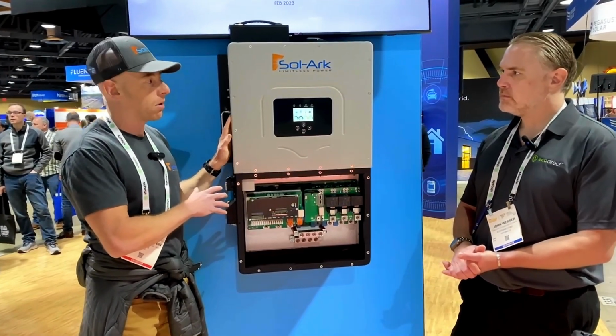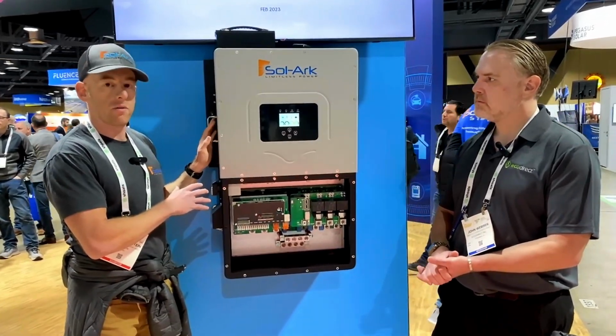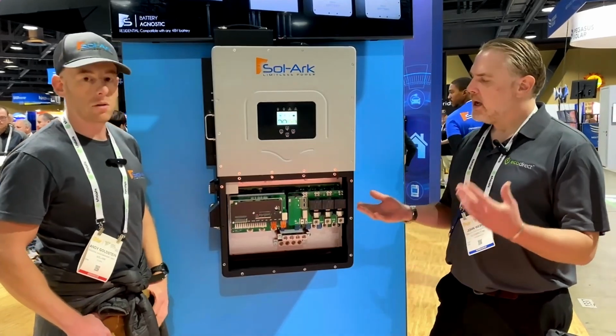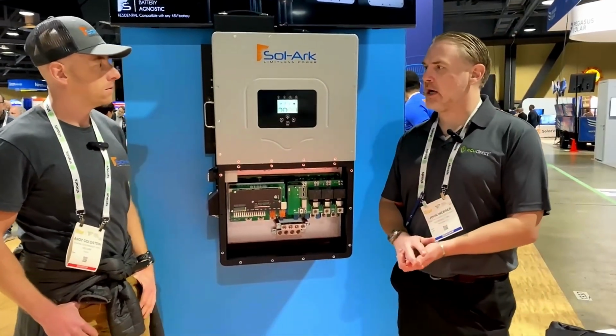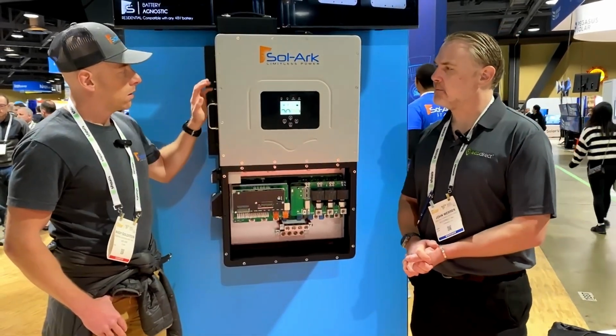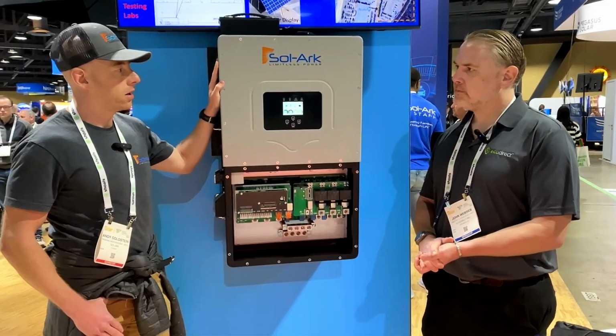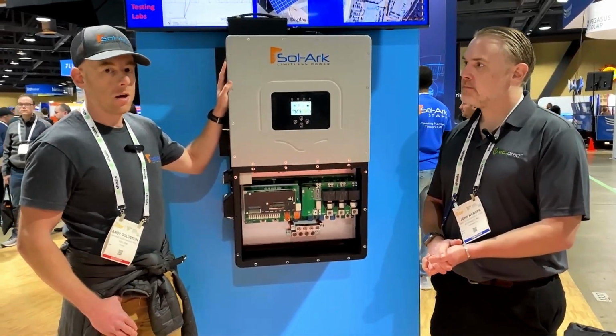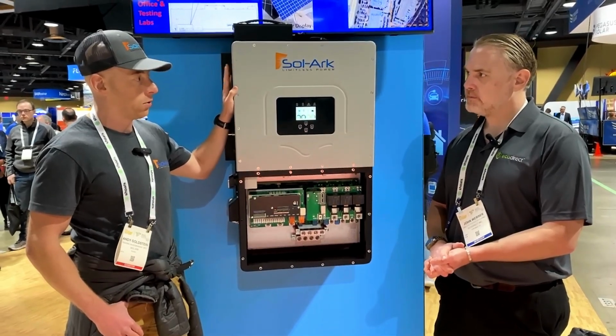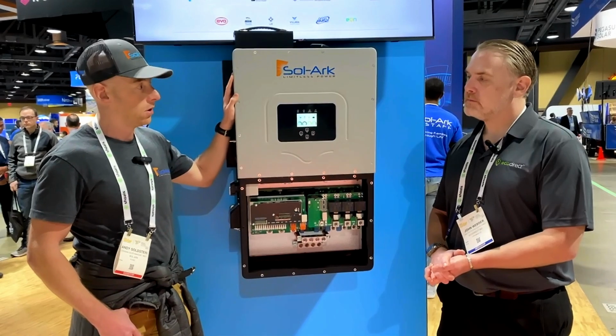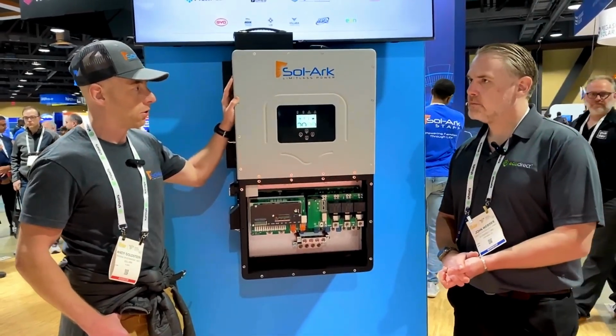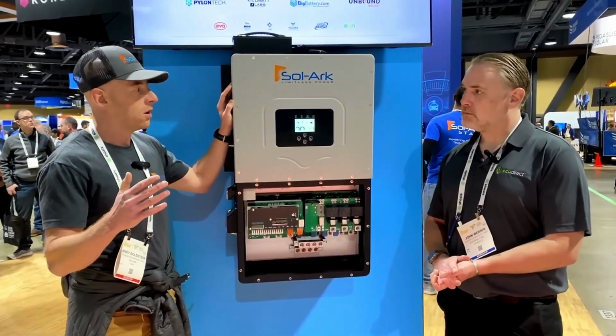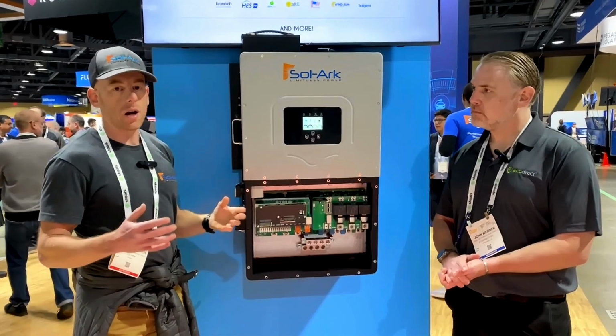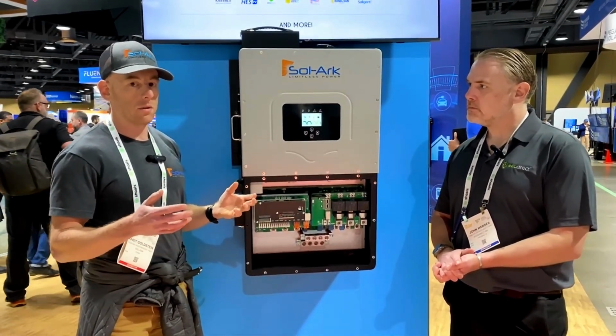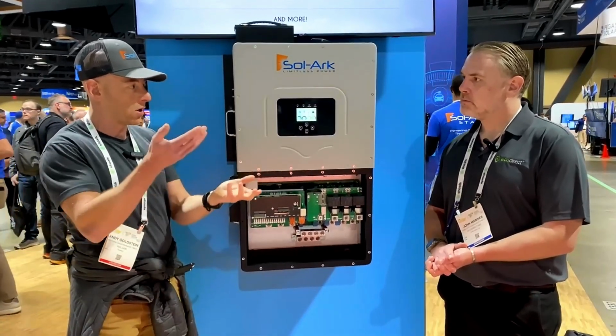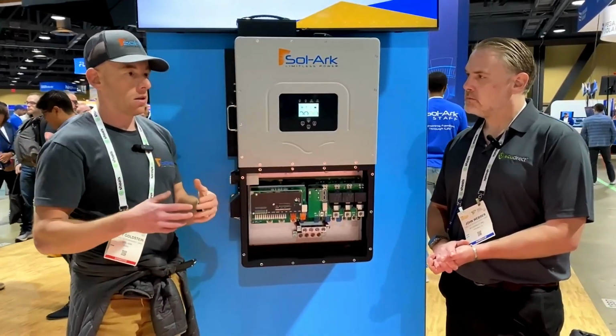Many of our existing battery partners on the low voltage side already have an option on the medium and high voltage side. So what is that voltage range, and is there an advantage to going to a higher DC voltage if a customer is trying to decide? The 30K will work between 300 and 600 volts nominal for battery, and our 60K inverter, which is a 480 volt service coming out in Q2, will be pushing past about 800 volts, so it'll be between 600 to 850 volts nominal. One of the advantages for high voltage is, when you have a lot less current - because of that inverse relationship, higher voltage lower current, or lower voltage higher current - you don't need as much copper.